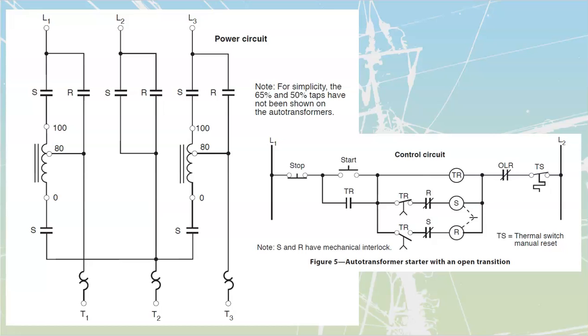Looking at our system over here, if we carry our power through, we can see that we would carry power up to there on our control circuit. And if I were to carry power through on my main circuit, I would see that I would have power carried through up to here. The instant that I press start, that start is going to close in, which is going to energize TR, which is going to seal that in. So the instant that we press start, we carry through to TR, out through our overloads. We've got the temperature sensor that's going to be inside of our autotransformers. And we see that that's going to seal in. These are instantaneous contacts that are tied to this timing relay.